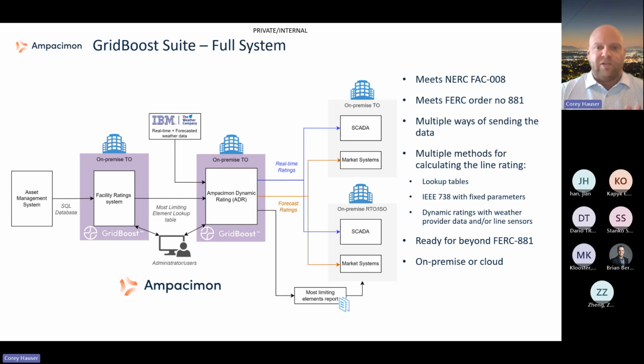What I wanted to get to was this overall image, showing how these two systems — our facility rating system and our Ampacimon dynamic rating system — can be brought together. Our Ampacimon dynamic rating system runs all the time, getting weather data, forecast data, sensor data, and calculating real-time and forecasted ratings. It takes all this, creates these ratings, does these calculations, and provides it out into EMS and market systems. This could be a standalone system that runs these calculations every five minutes, 24/7, 365, and provides this information to you.